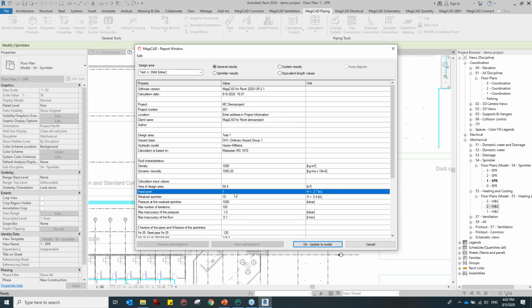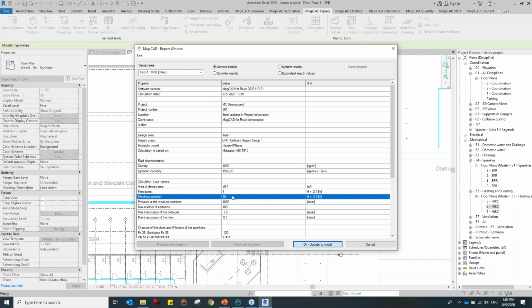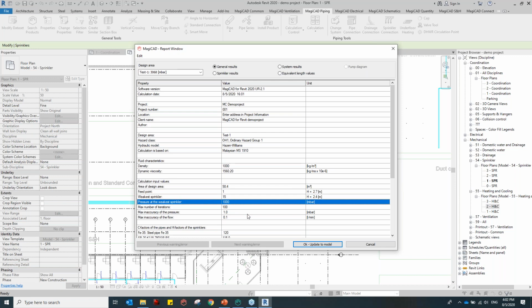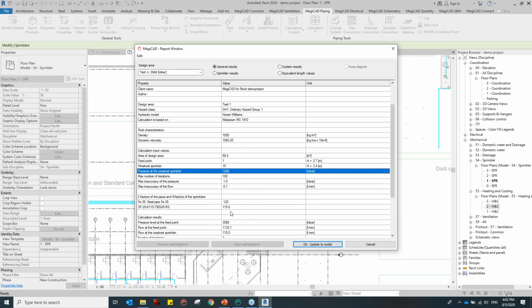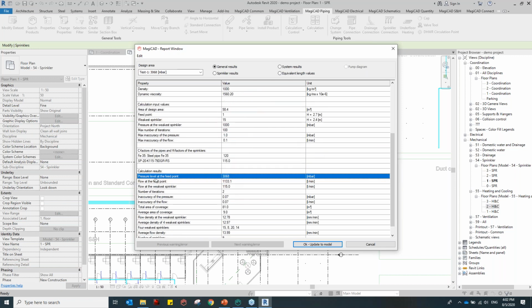Number 1 is the feed point, the weakest sprinkler is number 15, and the weakest sprinkler pressure is 1 bar. Here we can see the results: required pressure level at the feed point is 3 bar. I'm operating 9 sprinklers, so it requires 3 bar, which is okay.